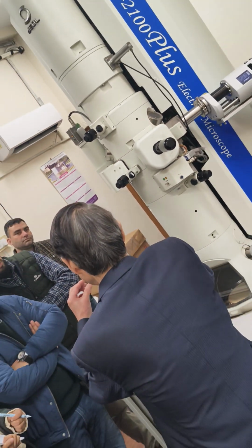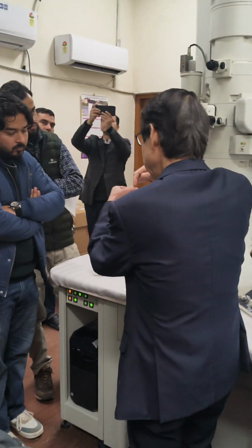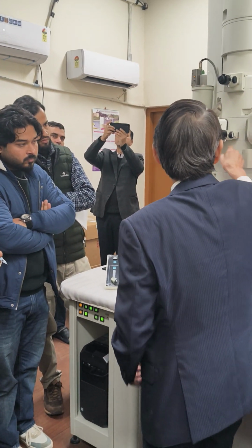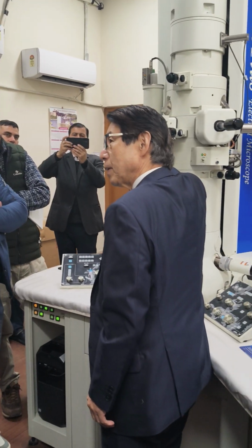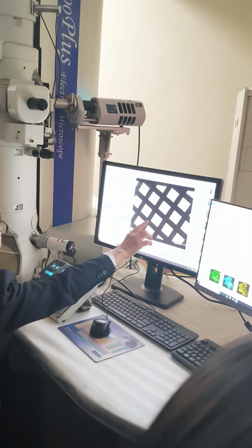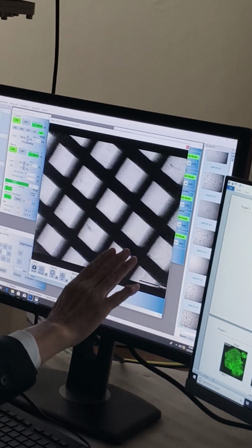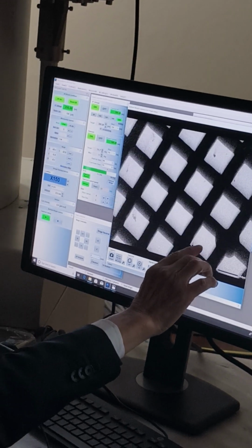Inside the objective lens, very close to the specimen chamber, there is a small metal fin. The fin is cooled down with the liquid nitrogen. Because the sample position changes like this.